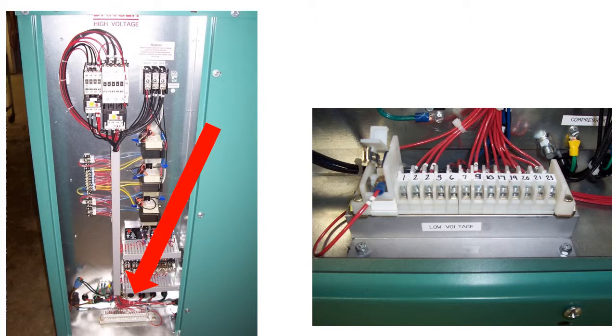All terminals with the same number are electrically identical. The 1s or 1As are the hot wire on the transformer, and the 2s are the transformer common.